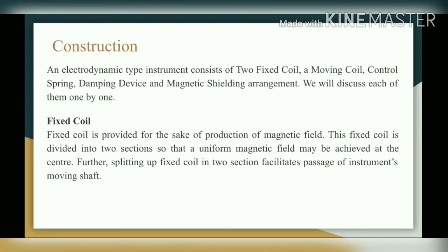Construction: an electrodynamic type instrument consists of two fixed coils and a moving coil, a control spring, a damping device, and a magnetic shielding arrangement. The fixed coil is provided for the production of a magnetic field. It is divided into two sections so that a uniform magnetic field may be achieved at the center, and splitting it facilitates passage of the instrument's moving shaft. In the middle of the fixed coil, the moving coil is placed.